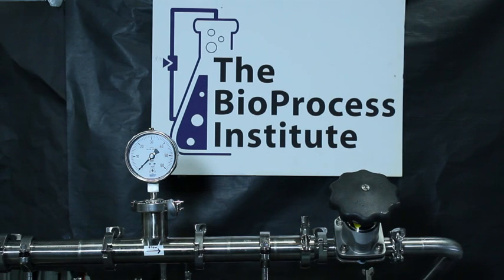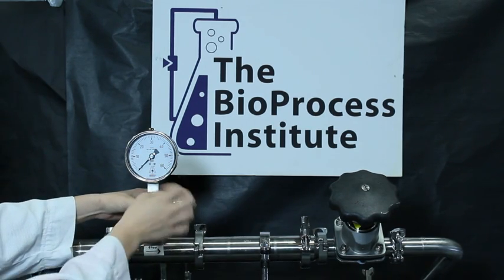Gauges are mounted in this upright vertical position to allow for ease of access for calibration and maintenance by technicians. Let's take off our gauge to do some routine maintenance calibration.